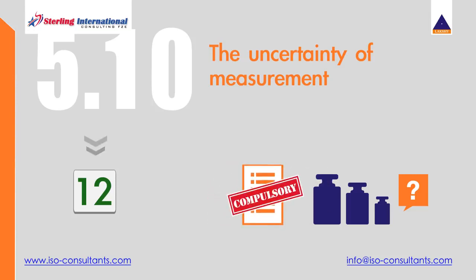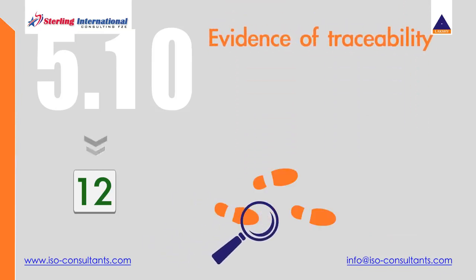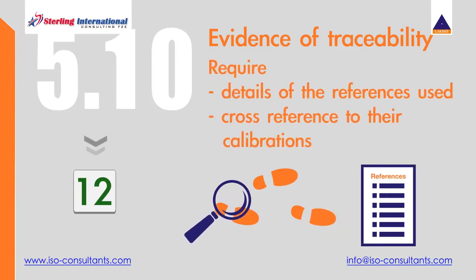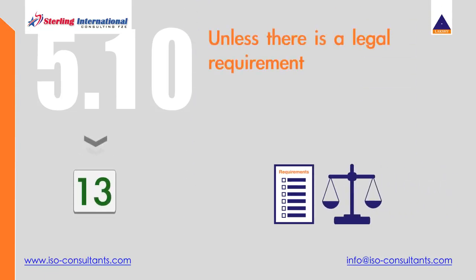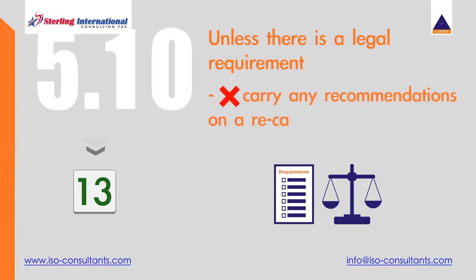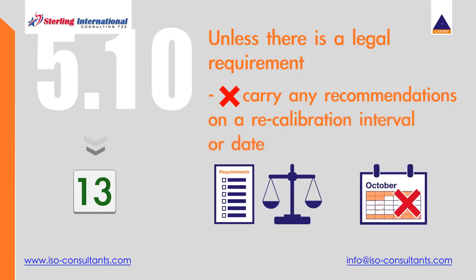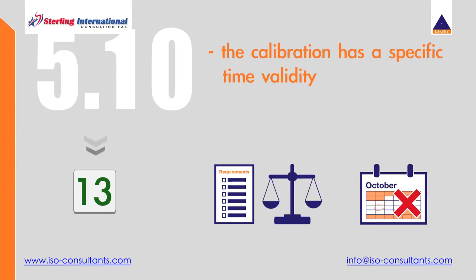Note that this is compulsory in calibration reports. 12. Evidence of traceability. This normally requires details of the references used and cross-reference to their calibrations. 13. Unless there is a legal requirement, calibration reports should not carry any recommendations on a recalibration interval or date, since this might be taken to imply that the calibration has a specific time validity.